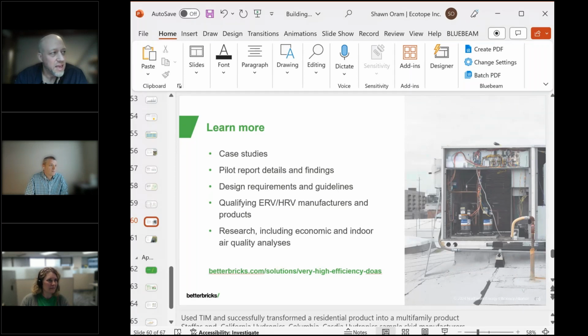Absolutely, I'll take a stab at this. I think that's actually one of the biggest value propositions for the VHE—you can eliminate any trimming that you do on that outside air. If you look at the cost to add the coil and that capacity to your plant, compared to the upgrade cost for the VHE, I've done this on commercial projects and looked at that delta—the VHE is actually a better life cycle cost number. The savings are always there. There's nothing to go wrong with a trim coil, no maintenance items associated with the coil and cleaning it. Once you factor in all of those items, I think it makes the case for going to the VHE DOAS. Chris, I don't know if you wanted to add anything to that.